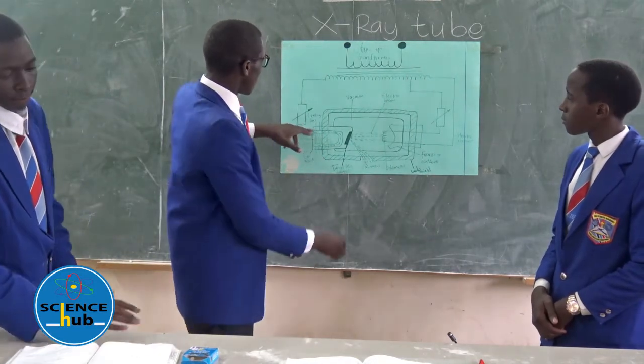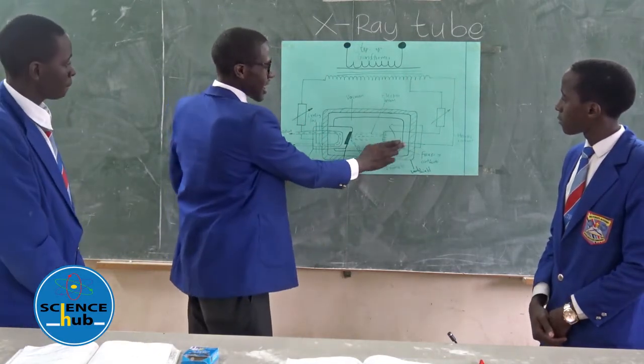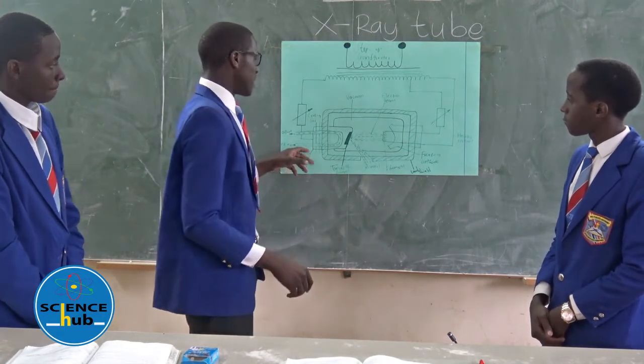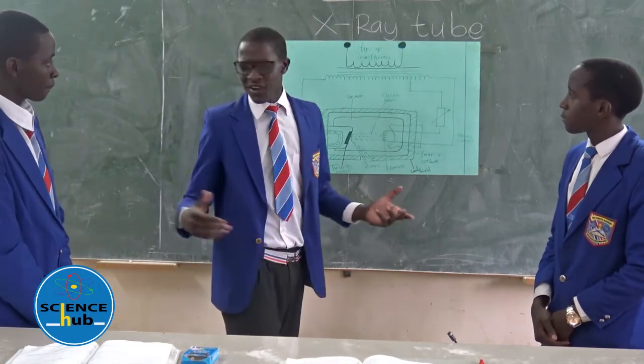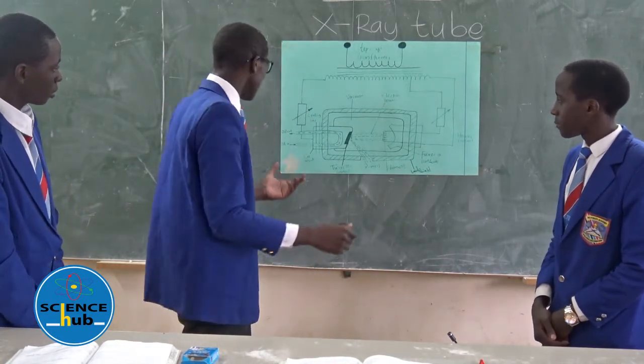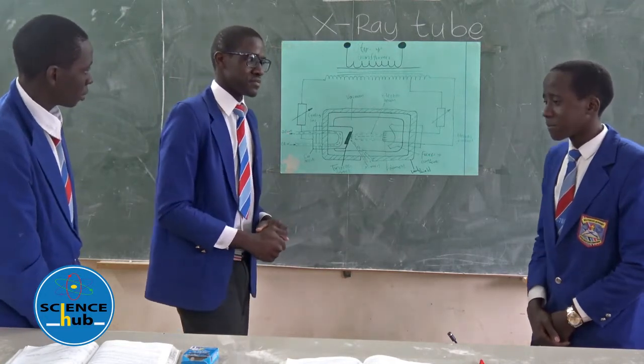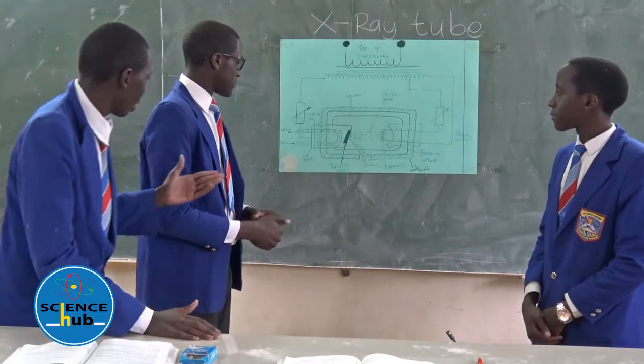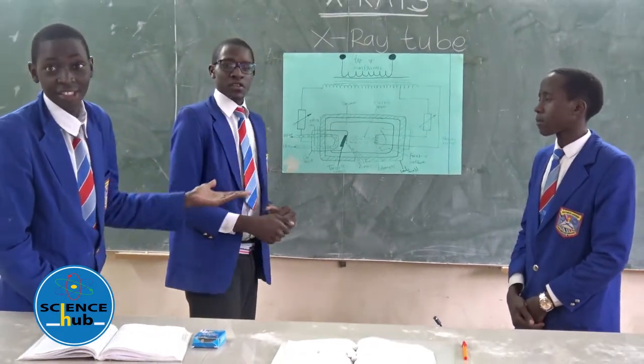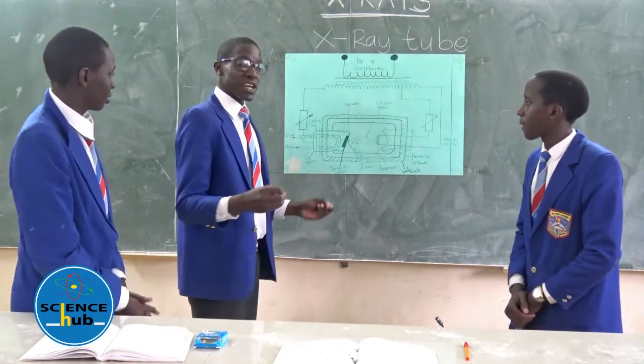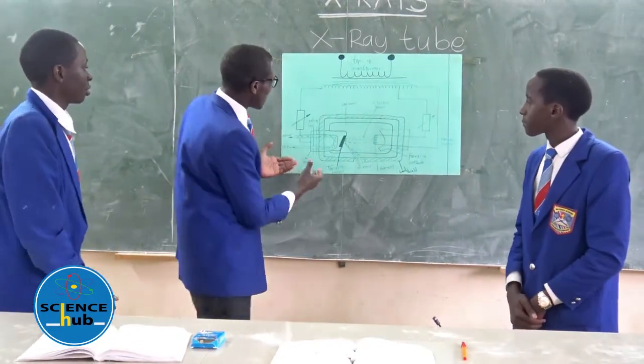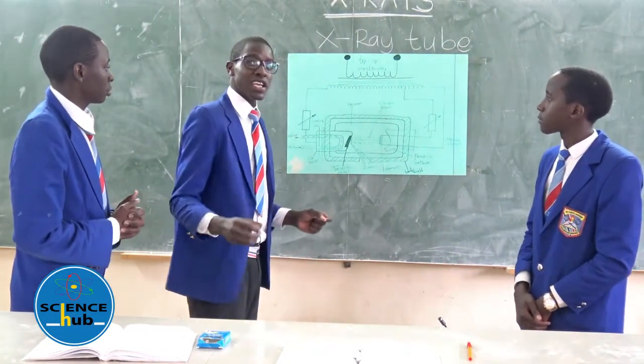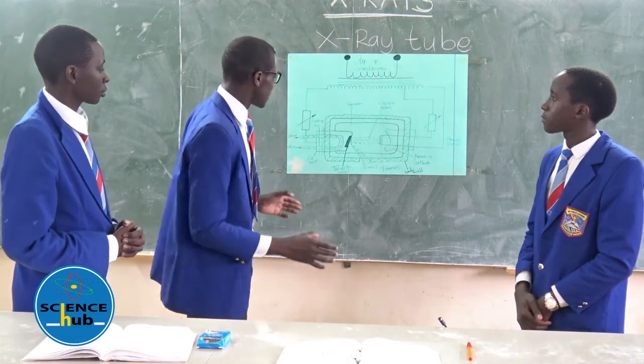We also have the anode, normally positively charged, made of copper. Why is it made of copper? Because copper is a good conductor of heat — copper has the ability of dissipating heat. For us to produce X-rays, there is a lot of heat production in the process.